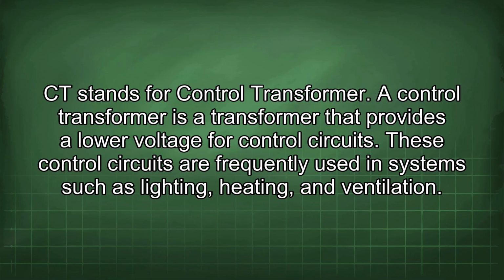CT stands for control transformer. A control transformer is a transformer that provides a lower voltage for control circuits. These control circuits are frequently used in systems such as lighting, heating, and ventilation.